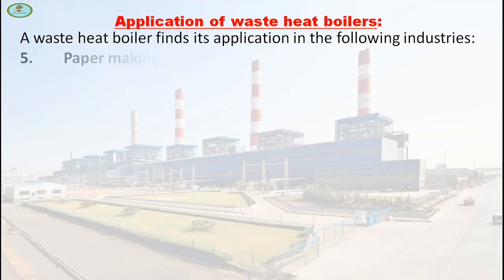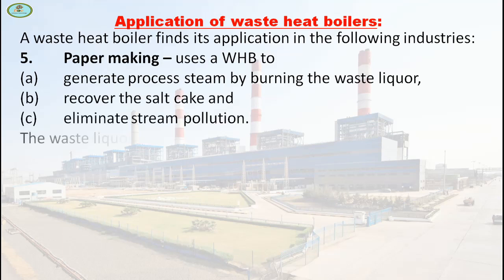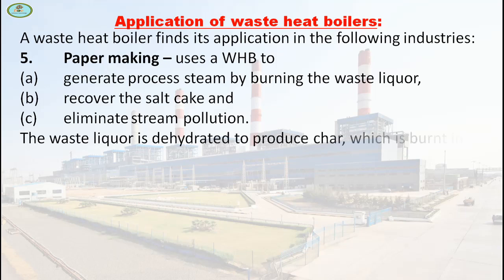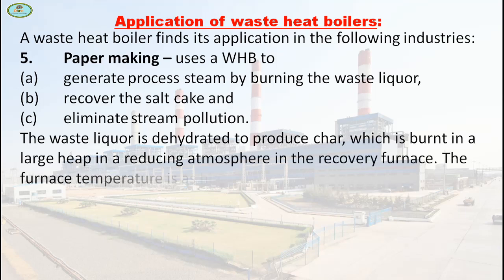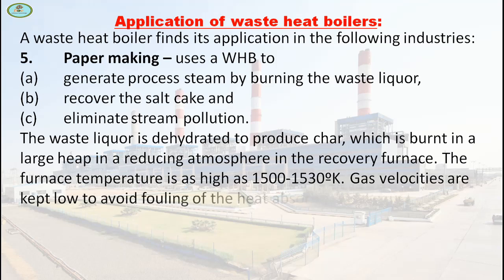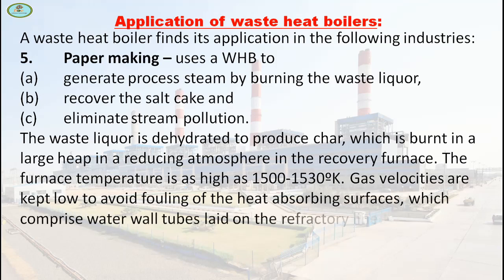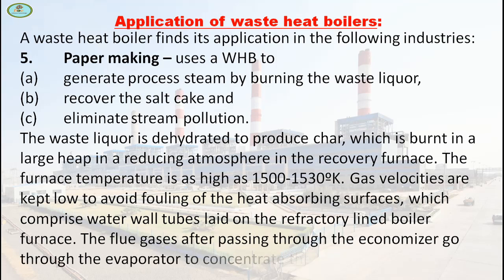Next is paper making. It uses a WHB to generate process steam by burning the waste liquor, recover the salt cake and eliminate stream pollution. The waste liquor is dehydrated to produce char, which is burnt in a reducing atmosphere in the recovery furnace. The furnace temperature is as high as 1500 to 1530 Kelvin. Gas velocities are kept low to avoid fouling of heat-absorbing surfaces, which comprise water wall tubes laid on the refractory-lined boiler furnace. The flue gases after passing through the economizer go through the evaporator to concentrate the black liquid.